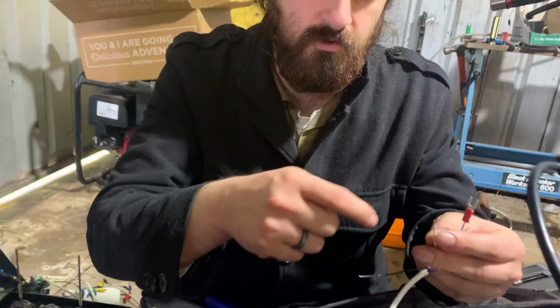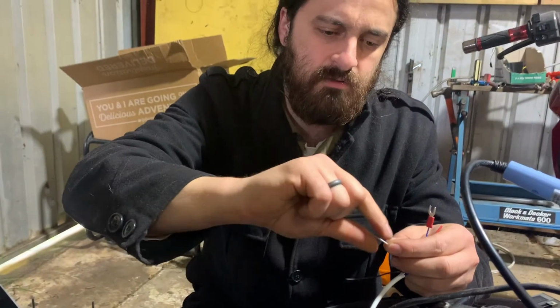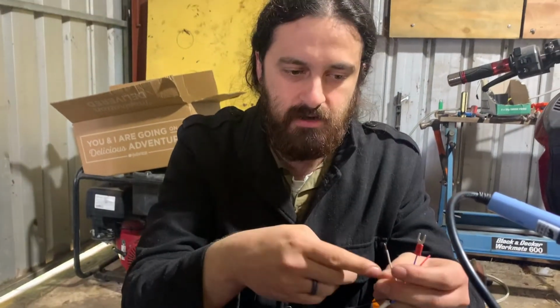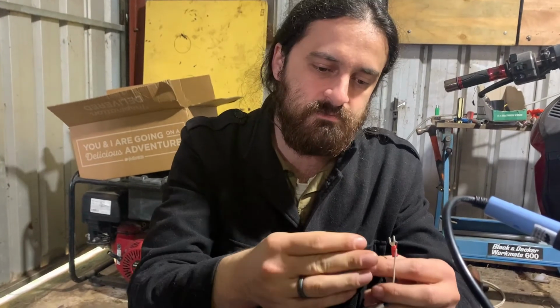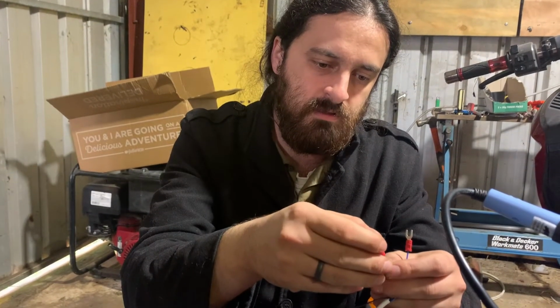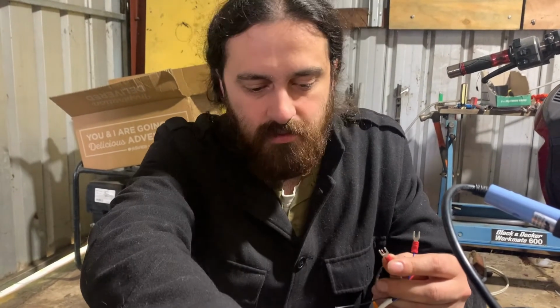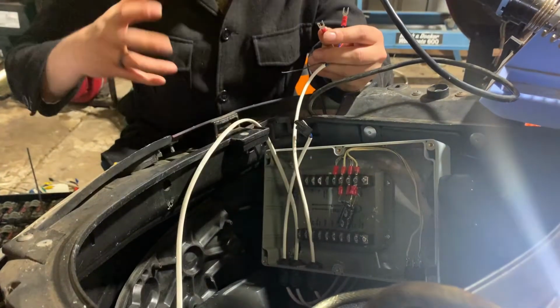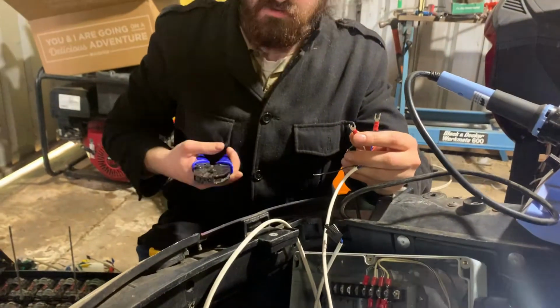Normally when you solder, the wire becomes brittle and hard, which means you need more mechanical protection to stop it from vibrating loose, because it work hardens really quickly. But because it's inside the box and the gland is already restraining it, it's not really as much of an issue.